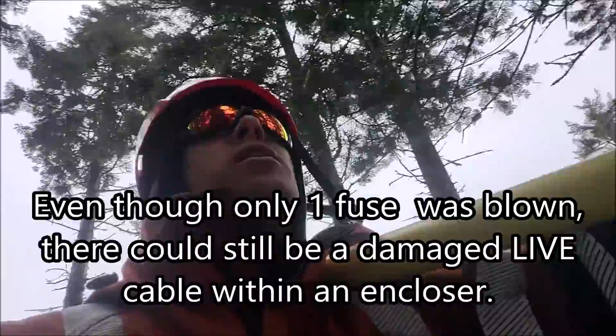We're going to be doing, before opening up these pad mounts for inspection, we're going to open the remaining two phases. There could still be a hazard where the other two phases are still energized. This particular three-phase underground feeds 3 splice pits and 2 three-phase pad mount transformers. Before I go and open the doors to those pad mounts, even though they're dead front pad mount transformers and you are allowed to open them while energized, you should not be opening them when there is an unknown situation, a fault in the line, or suspected fault within it.